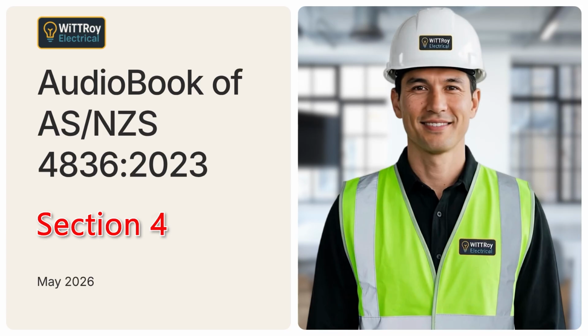A voltage tester must be used immediately before work to prove that the capacitors are discharged. The voltage test must be done on the DC scale of the tester. DC means direct current. If a capacitor is not discharged, then the requirements for work on or near exposed energized conductors, or live conductive parts, apply. Care must also be taken when applying discharging devices because arcing can occur. Capacitor terminals must not be short-circuited or earthed using metal objects such as spanners or screwdrivers. That method can cause electrocution, arcs, flash burns, or electric shock. Only suitable devices should be used for the work.